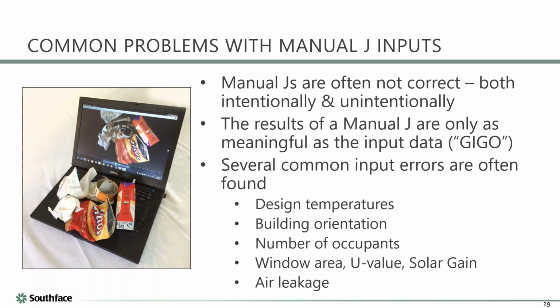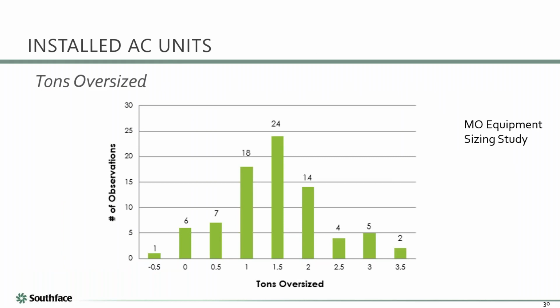In terms of load calcs, without going into it, probably people have heard the term garbage in, garbage out. Manual J is a tool. If you put in garbage numbers, you can make it spit out whatever load answer you want. So it's a tool, you've got to use it correctly. And we've definitely seen cases of people either accidentally or on purpose putting in wrong information. I saw a load calc that had Atlanta's outdoor design temperature of 110 degrees. I saw a load calc that had a 3-bedroom house with 15 people in it. And all the windows faced west, and the windows were all single pane metal frame windows. And I don't know, leaky, I'll just pick very leaky, and that will have a big impact on heating. So these are just typical things. So it's a tool, you've got to use it correctly, and then you should be in good shape.